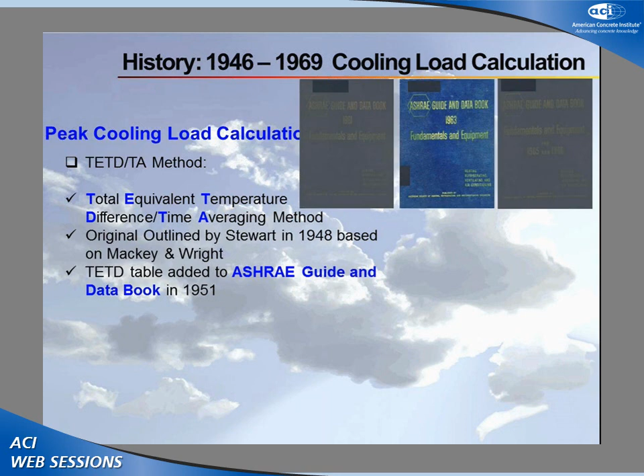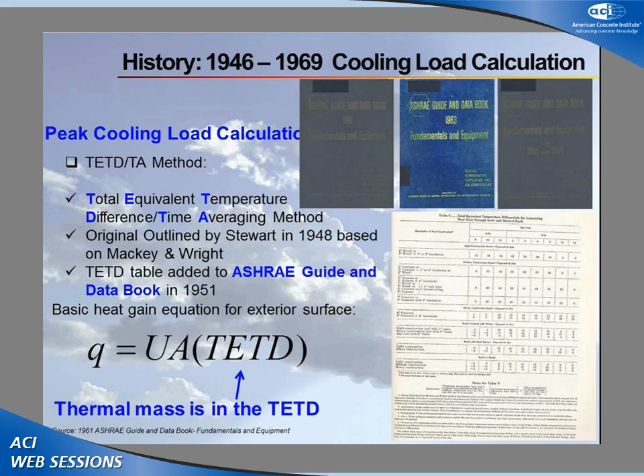Further along that line, if we take a look at the actual peak cooling load calculation, the total equivalent temperature difference method based on Mackey and Wright was tabulated by Stewart in '48 into the tables that showed up in the handbook. And as I mentioned earlier, thermal mass actually showed up as an adjustment to the temperature difference in the peak load calculations.